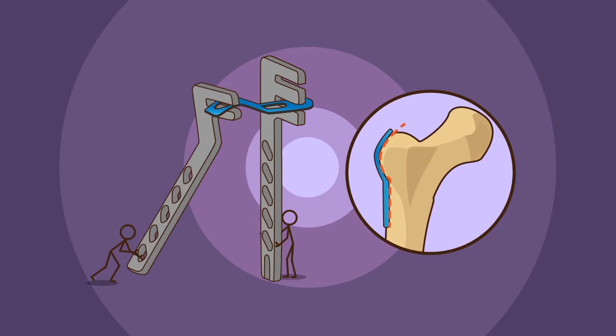Long plate bending: this step pertains only to the long plate. Using the two-plate benders, bend the plate to conform to the femur's geometry. The long plate should not be excessively or repeatedly bent, and should not be reverse bent in the same location. Use care to ensure that the plate is not scratched or notched during the bending process.